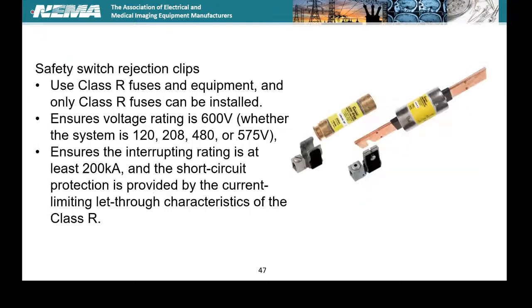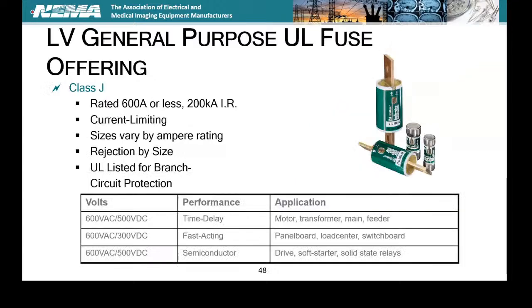This just shows the clip, so I'm just going to go on to the next one. Class J fuse. All right, I'm a little bit of a delay from you. So Class J, so again, now you're moving up in amp rating. We started at the Charlie Chaplins, the Class CC fuses that only go up to 30 amps. Now we're moving up into 600 amps, current limiting, 200,000 amp interrupting rated devices. These again are rejection by size.